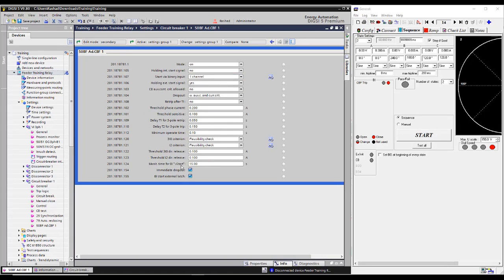If you give the relay initiation and before 15 seconds pass, the relay does not see current or does not see the breaker close, depending on whether you are in current mode or not, in this case it will show you a binary input fail alarm and the breaker failure will not activate. That's what happens. The guys give initiation and this setting might have been 3 seconds or 5 seconds or whatever, and he started to raise the current. So of course the time has already passed and therefore it will not work after this time.